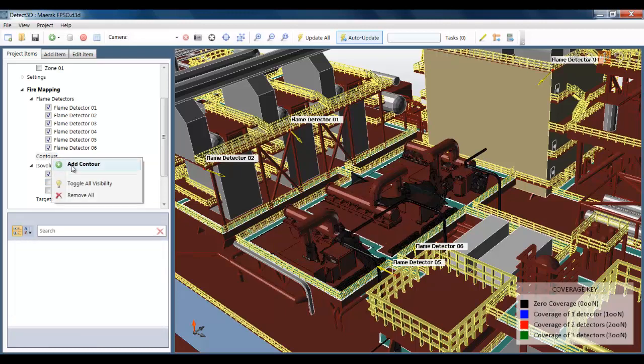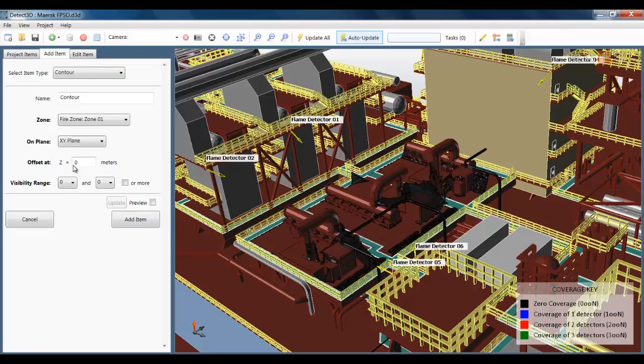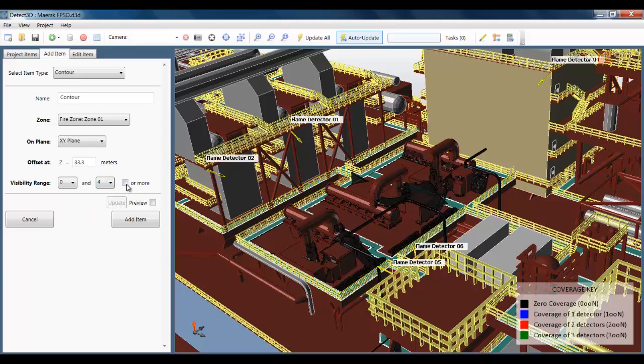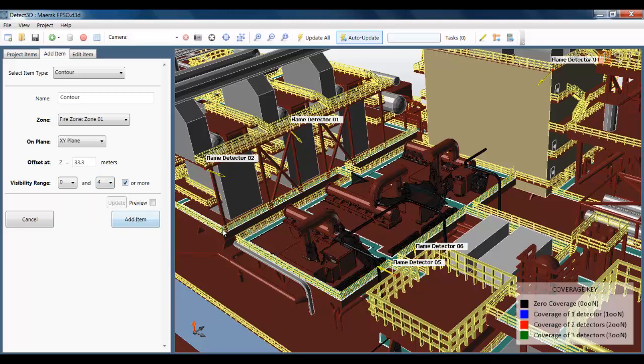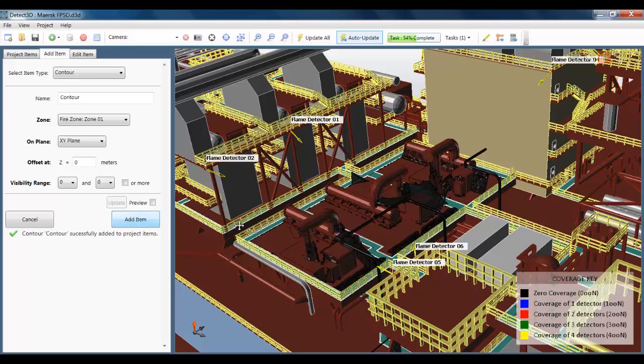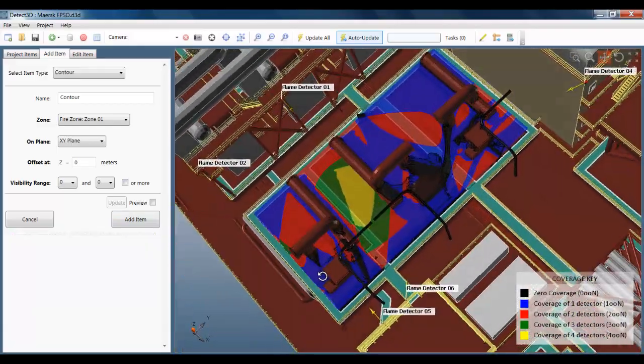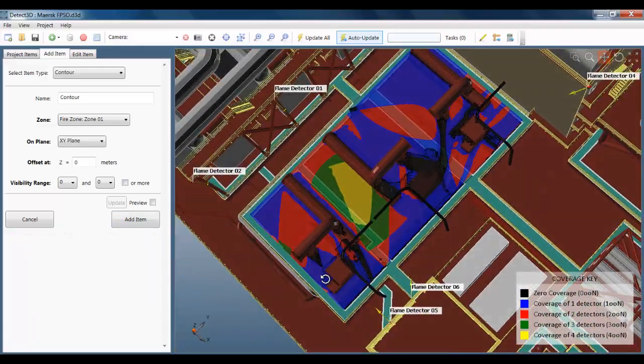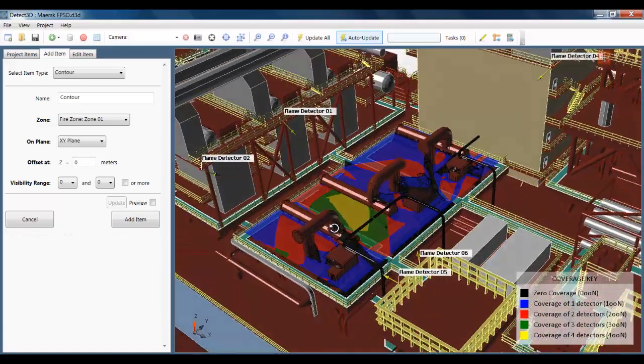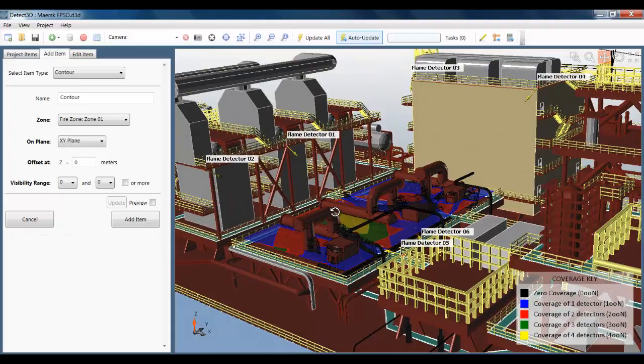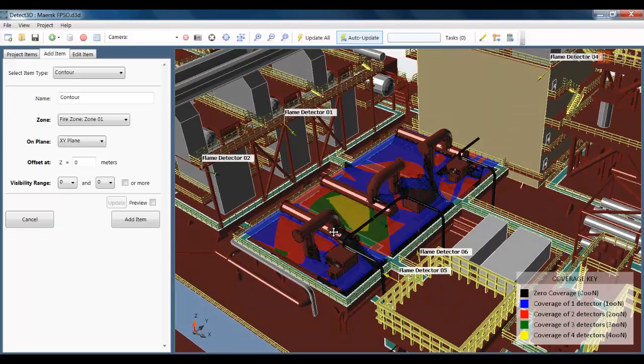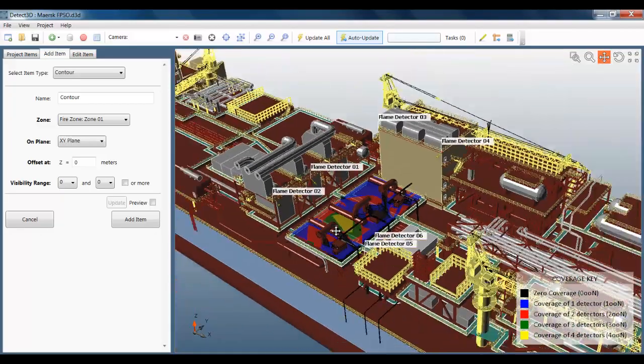I can also use contours to visualize the results. Here I'm going to add one at one meter above the base of the fire zone, which is 33 meters. I'm going to add that to the project. And we can see the coverage results on that horizontal cut plane. So I've got a pretty good flame detector layout and I've added some visualization. So now I'm going to follow through with the project to the outside world. And we've worked hard to make this possible for you to do.